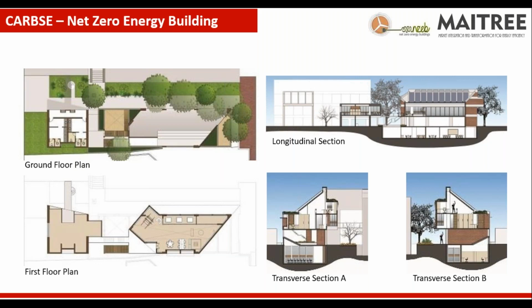The basement is a completely air conditioned space, having radiant cooling and a dedicated outdoor air system. Then a ground floor which is semi-open, which floats with the outdoor all the time. And on the first floor we have our laboratory equipment and a few researchers, and the mezzanine is primarily desk space where about 22 researchers sit. So that's a volume we are operating in mixed mode. That means the basement is air conditioned, the ground floor is naturally ventilated, and the first and mezzanine floors are operated in temporal mixed mode. So this is what you see in the longitudinal and cross sections.